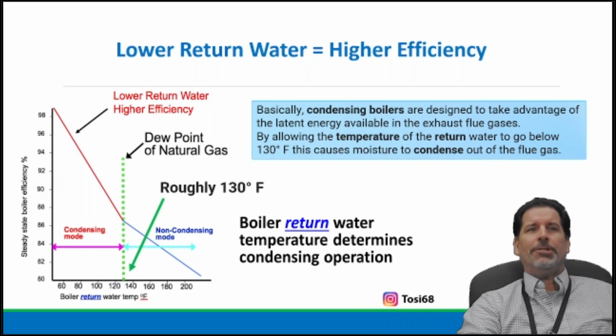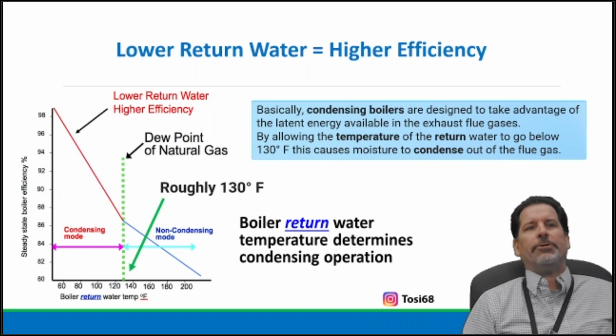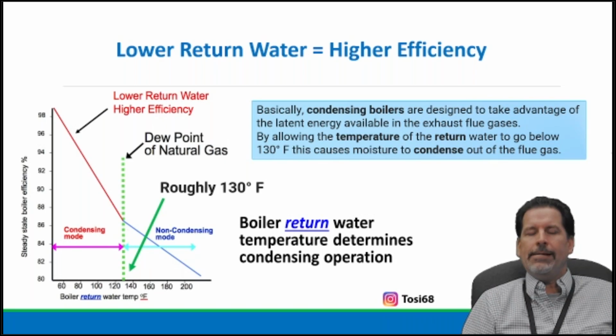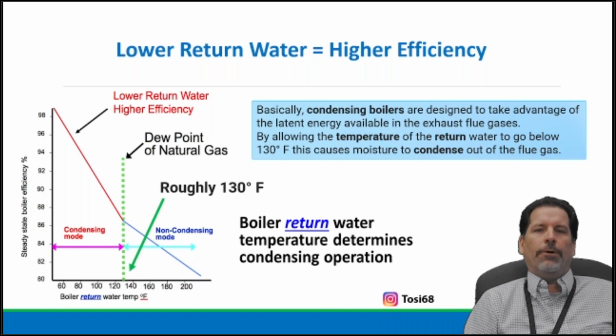Again, I asked the question about the radiant. What's the lowest water temperature maybe you've ever supplied radiant to? But it wasn't the boiler being set for that water temperature. You probably had a mixing valve, right? So now we're asking the appliance, the boiler, to have that lowered water temperature off of the burner itself, the heat exchanger, the system, right?